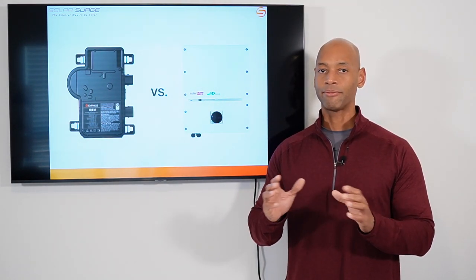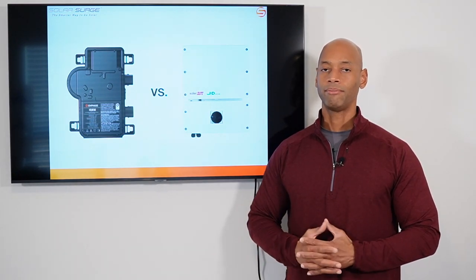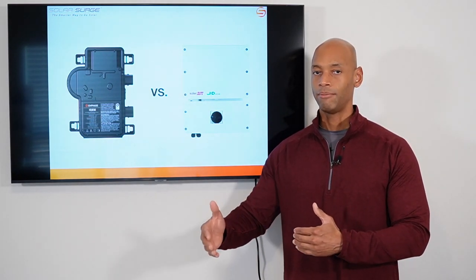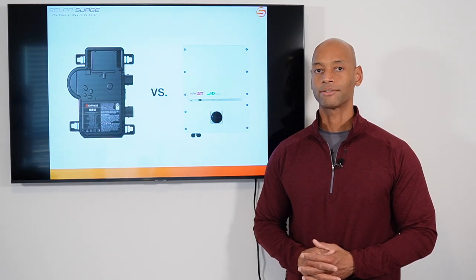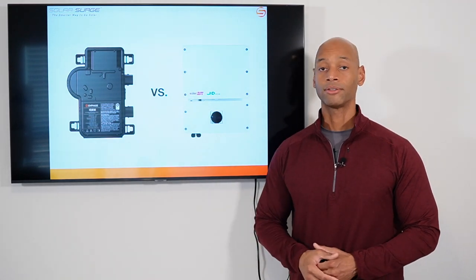Again, 20-25% oversizing is okay. Anything beyond that you may begin to ask questions and may want to bump it up a level in terms of the size rating. But SolarEdge generally does have the advantage in terms of clipping loss.